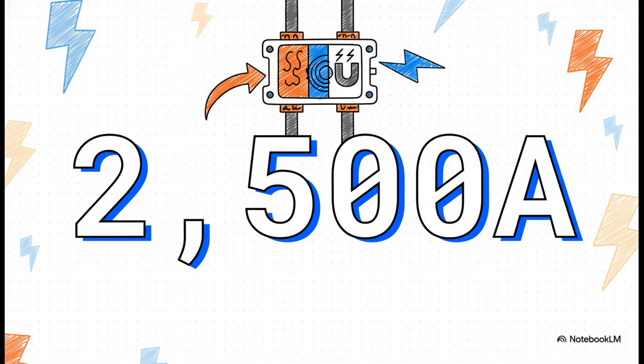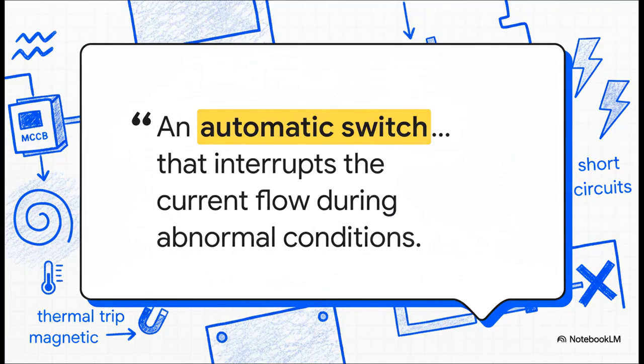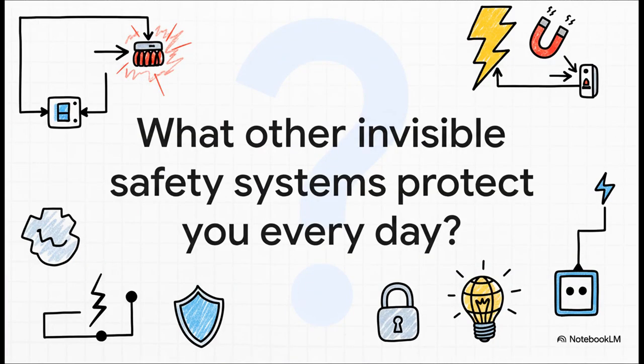And just to give you a sense of scale here, some common MCCBs are rated to handle up to 2,500 amps. I mean, that is a staggering amount of power, easily enough to run a small factory or a big office building. And this one device is designed to safely cut that flow in the blink of an eye. So at the end of the day, it all comes back to this one simple, elegant function. It's an automatic switch that interrupts the current flow during abnormal conditions. It's such a simple concept, but it protects billions of dollars of equipment and, more importantly, countless lives every single day. The MCCB really is a masterpiece of engineering, working silently in the dark.